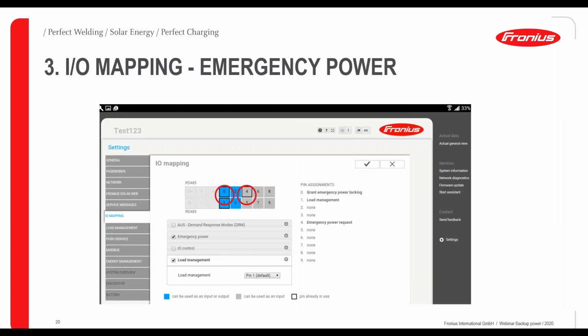Yeah, then the third step is the I/O mapping. For the I/O mapping, you need to first connect your laptop or your smartphone with the Wi-Fi access point of the inverter. So first you open the access point, connect with your smartphone, and then go to settings and here to I/O mapping. And in I/O mapping, you have to adjust the emergency power mode. So you just click on emergency power here and then save these settings here. So that's actually all that's needed. So you need these pins 0, 4, and 5 for the emergency power mode. So that's the I/O mapping.